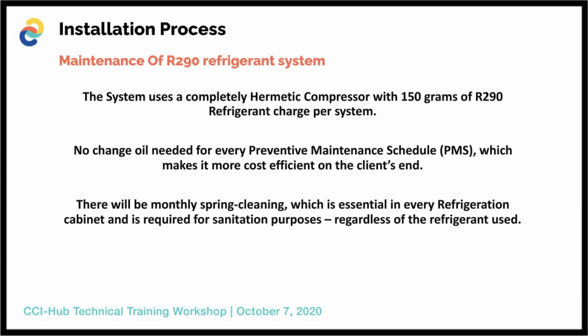Maintenance of the R290 refrigerant system. The system uses a completely hermetic compressor with a 150 grams R290 refrigerant charge per system. No oil change is needed for every preventive maintenance schedule, or PMS, which makes it more cost efficient on the client's end. There will be monthly spring cleaning, which is essential in every refrigeration cabinet and is required for sanitation purposes, regardless of the refrigerant used.